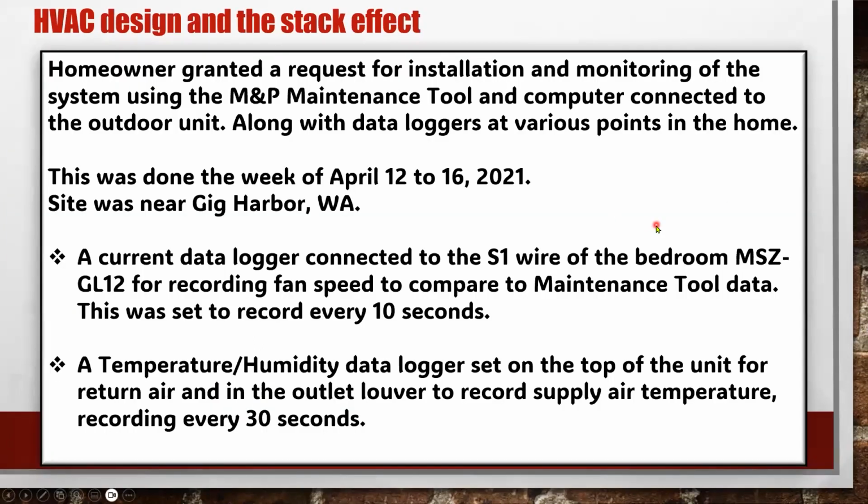The homeowner granted me a request to install and monitor this system using some data loggers so I could see what was actually going on, along with connecting our M&P maintenance tool to the outdoor unit. I wanted to be able to tie all the actual temperature readings within the home to what the unit was actually doing. And this was done the week of April 12th through 16th, 2 years ago, 2021. The site was located near Gig Harbor.